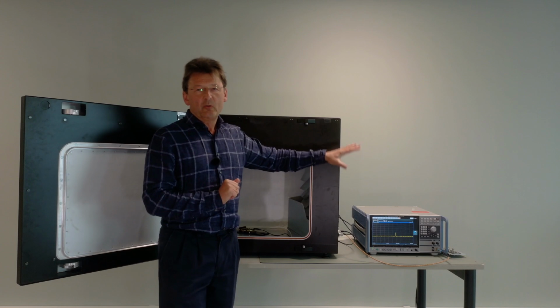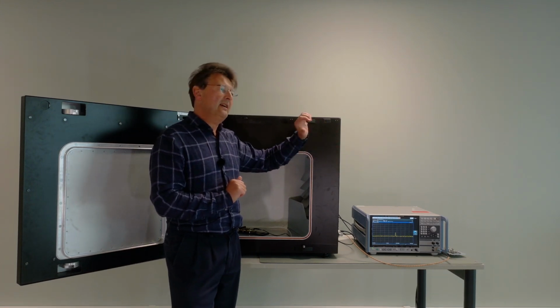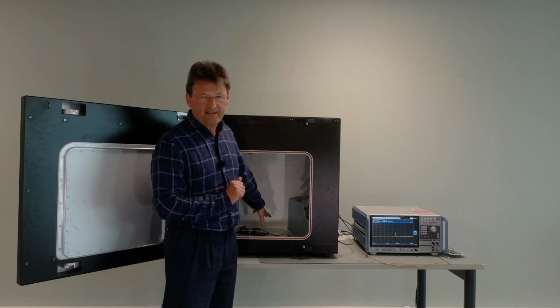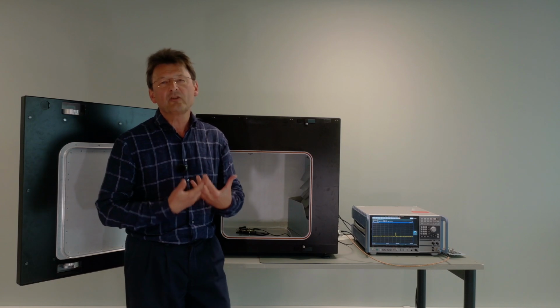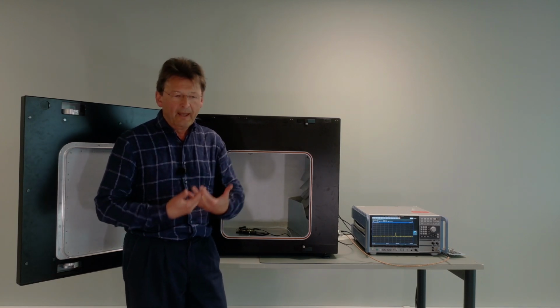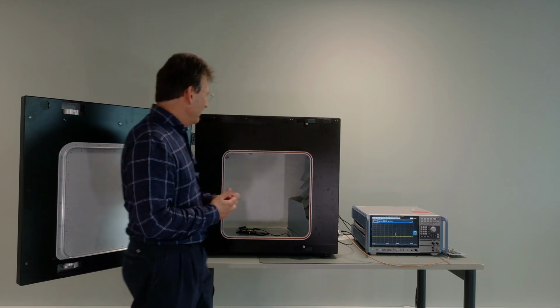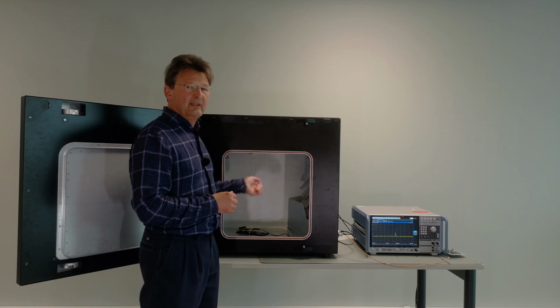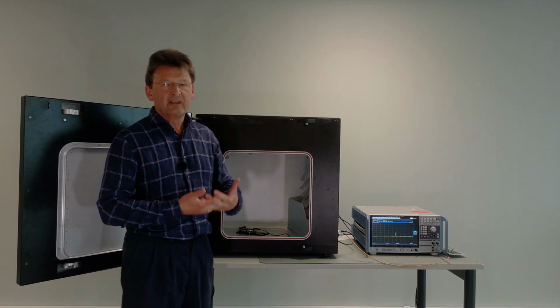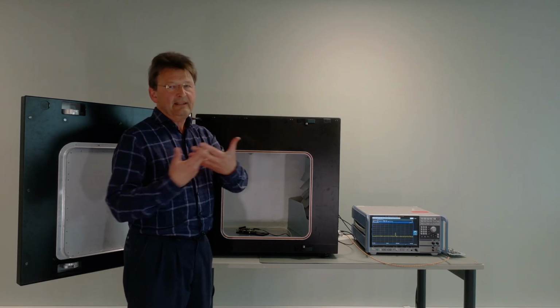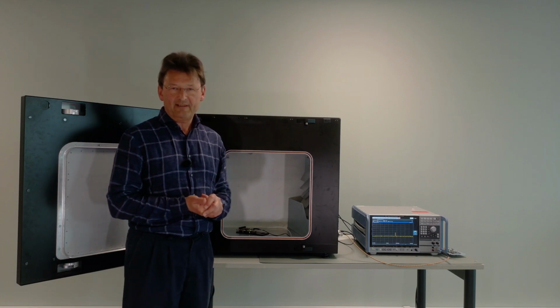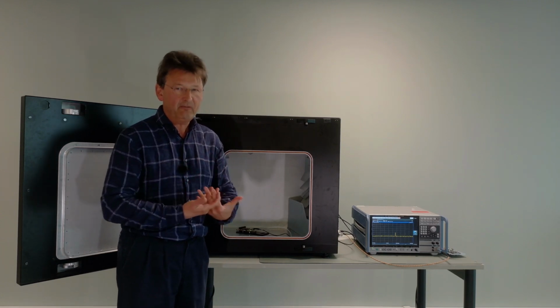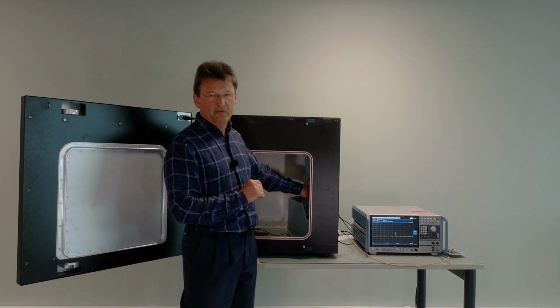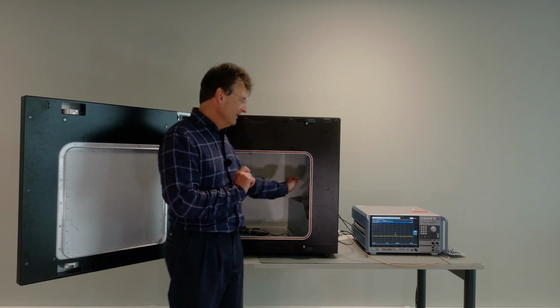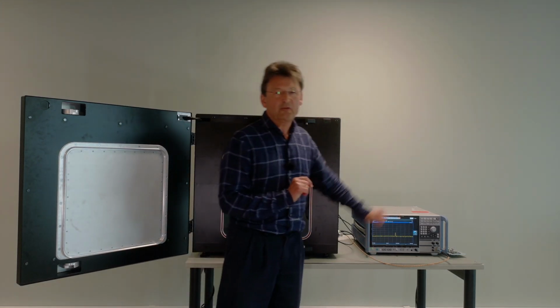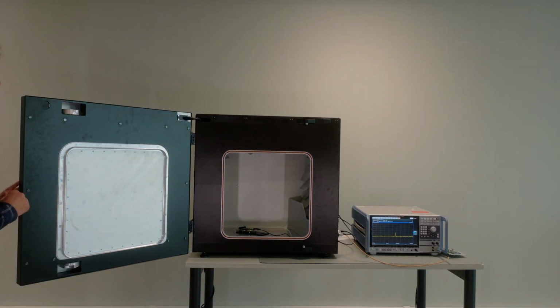Now, when you are going to measure with a spectrum analyzer, you also need to do an additional calibration. Why? Because the device under test by itself, even when it's not active, is going to change the loss properties of that chamber. And to characterize that, there is a calibration module foreseen in the chamber on top that allows us to measure the difference between factory cal and, in fact, when you are putting in that device under test while it's inactive. As soon as that calibration is done, at that moment, you also need to take into account the type of antenna you're using as a reference antenna, and you need to take into account the coupling to the spectrum analyzer. So let's come to the outside.